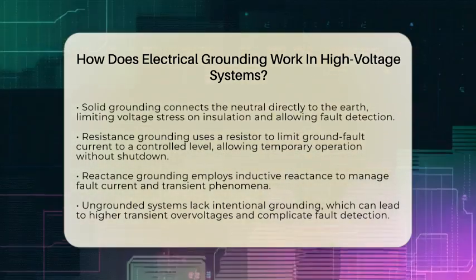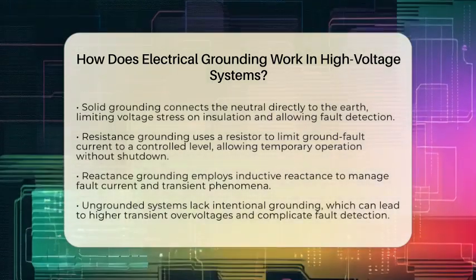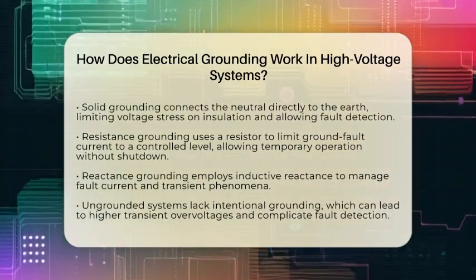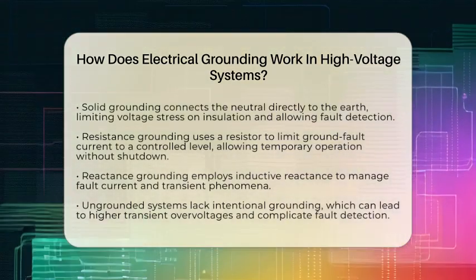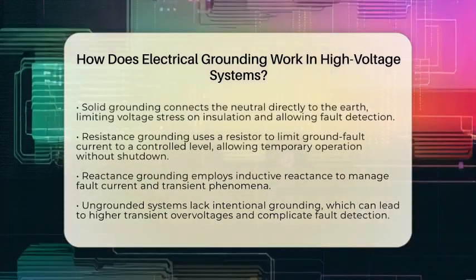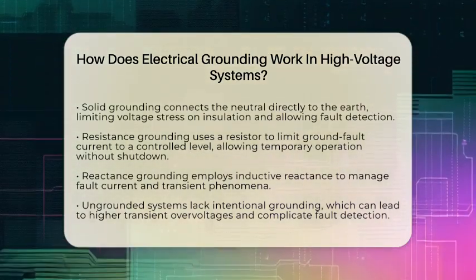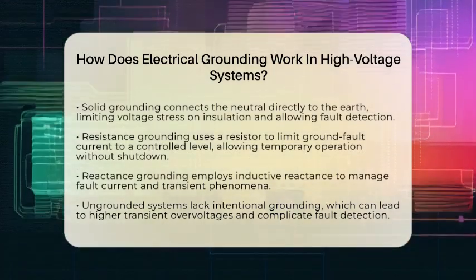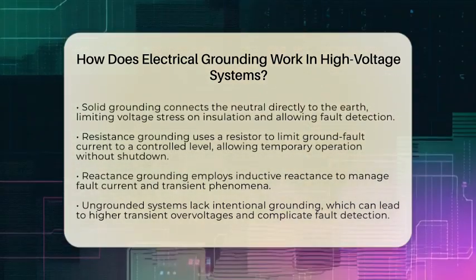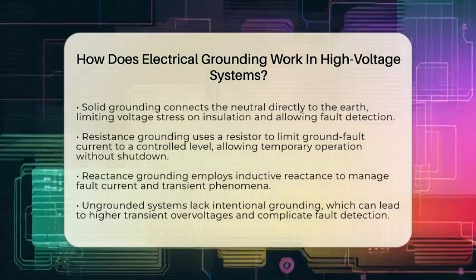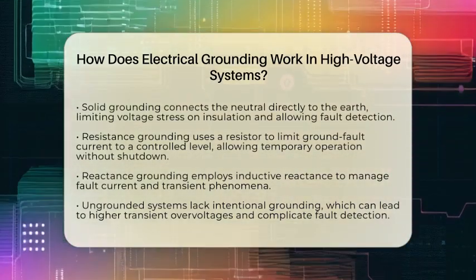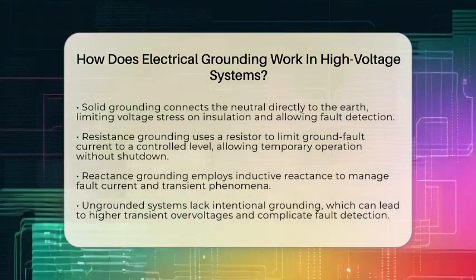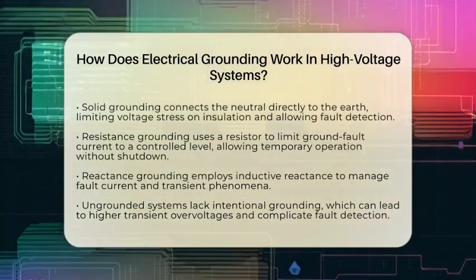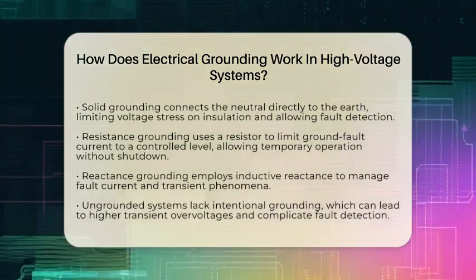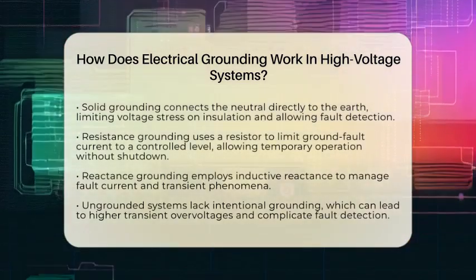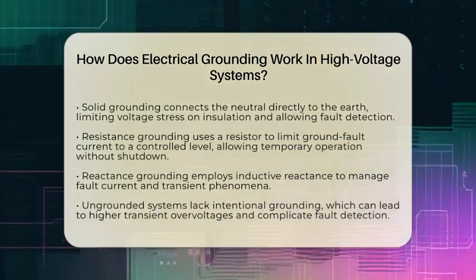Another method is resistance grounding. In this case, a resistor is placed between the neutral and the earth. This limits the ground fault current to a controlled level, typically around 10 amps or less. This approach reduces damage at the fault point and allows the system to continue operating temporarily without shutting down immediately. Reactance grounding is another option. This method uses inductive reactance in the neutral-to-ground connection to limit fault current and manage transient phenomena.